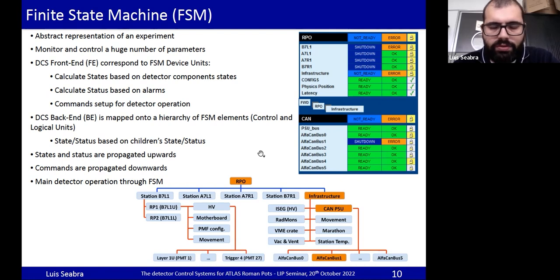And when we want to send a command, in this case, for example, if we want to switch on the high voltage, it doesn't make sense to go item by item switching on the high voltage. We do it by sending a command through the top of the FSM and then propagate it downwards the hierarchy. This is how we propagate and control, monitor everything from the DCS side.